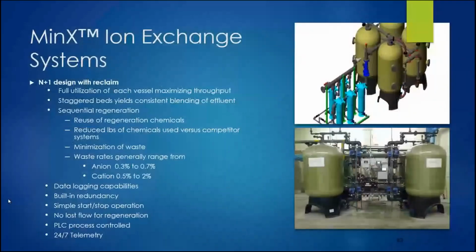A variation of this and a less expensive version of the Simpex system is a MinX. The MinX system is designed to have n number of vessels for the service flow, but it's also to recapture the regenerant as it's used in the process, and use that again to increase the capacity associated with the system.